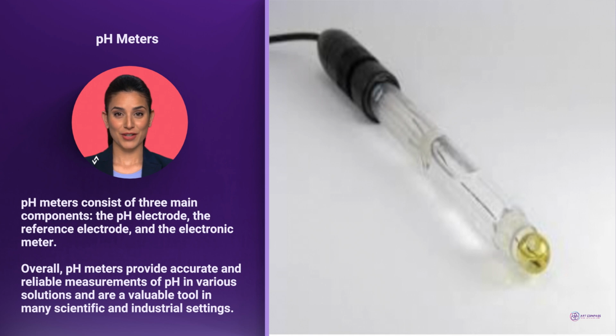The reference electrode is a silver-silver chloride electrode that is immersed in a potassium chloride solution. The electrode generates a stable voltage that is used as a reference for the pH. The electronic meter is the final component of the pH meter, which is responsible for converting the voltage generated by the pH electrode into a pH reading. The meter displays the pH reading on a digital screen or a dial.